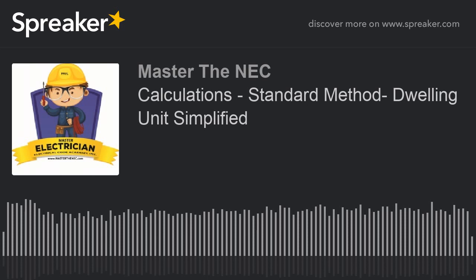The maximum demand in kW, which is synonymous again with VA. So 8 kW is 8,000 VA. And guess what? That's the next number we put on our piece of paper. It's 8,000 for that 12 kW range. All right, we're moving along pretty good now.